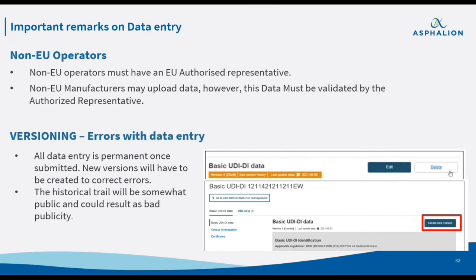And now, I'm just ending. Before closing the session, here are some important remarks on EUDAMED data entry. As I mentioned before, non-EU economic operators must rely on EU authorized representatives. That was regarding the first section, when I talked about the different user profiles in the EUDAMED database. All the data registered by the non-EU manufacturer, for example, has to be validated by an authorized representative.